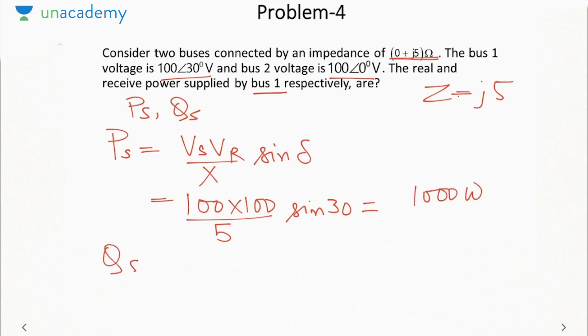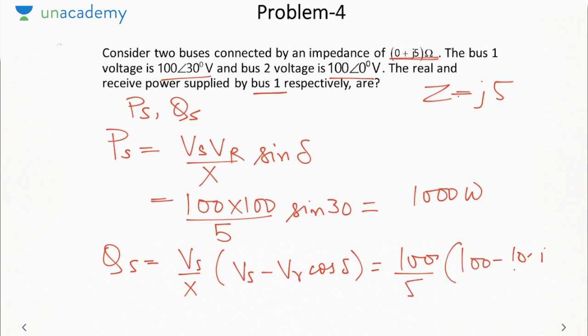And QS, when resistance is neglected, is Vs by X times Vs minus VR cos delta, that is 100 by 5 into 100 minus 100 cos 30. So this comes out to be 268 VAR. These expressions for real and reactive power at both the sending and receiving end, when the resistance of the line is neglected, are very important. You can remember the general expression for PR and QR, but remember the special cases of PR, QR, PS, QS for when the resistance of the line is neglected and it is a short transmission line.